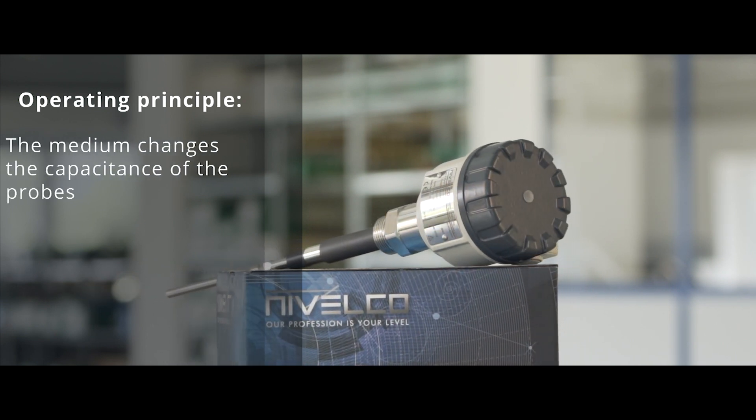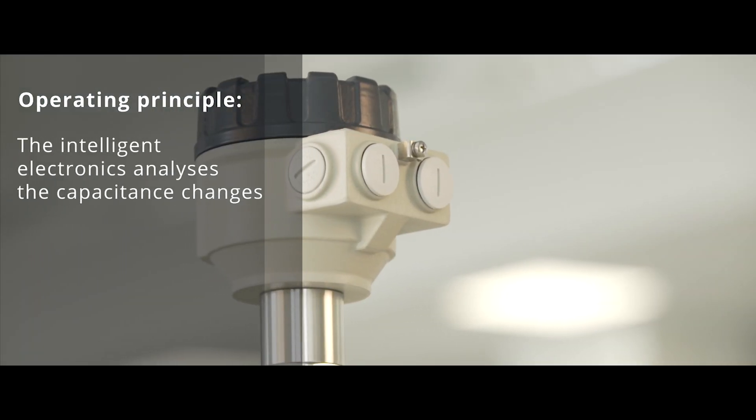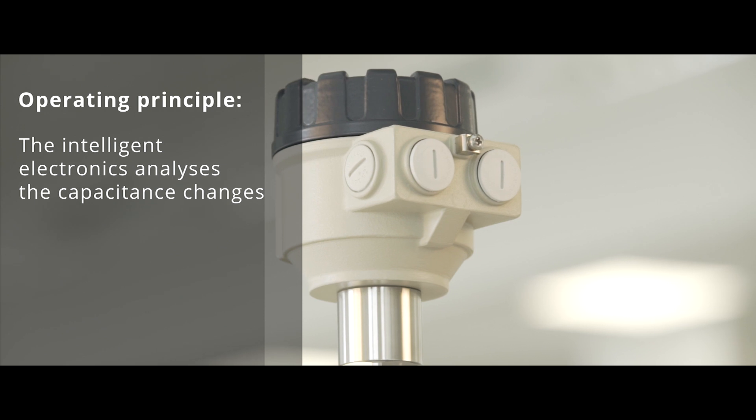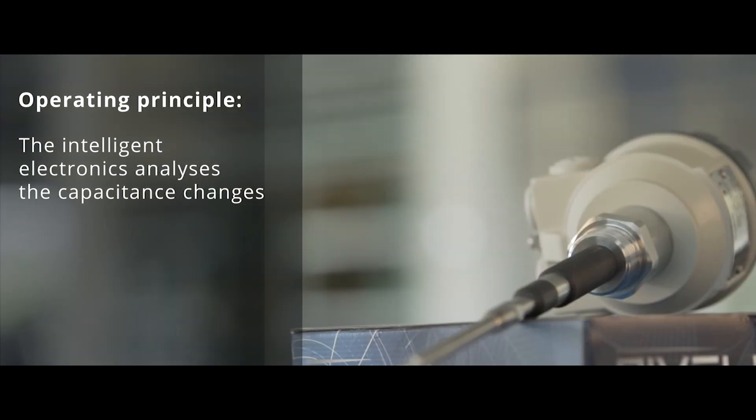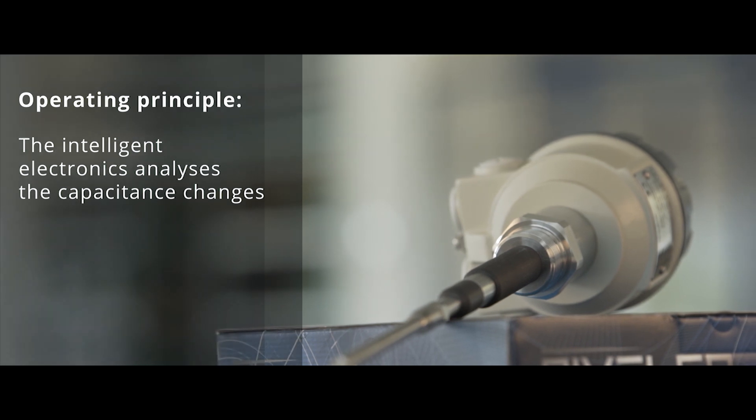When the medium reaches the probe, the capacitance value will increase. The intelligent microcontroller-based electronics of the NivoCAPCK continuously analyzes the voltage level proportional to the capacitance difference between the two probes and the housing.